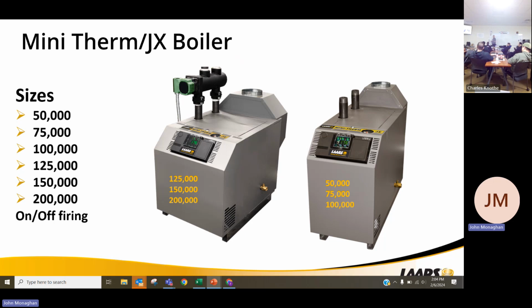Unlike the condensing products, it's on-off. There is no modulating. It's all the firing rate all the time, regardless of what is calling. One of the things I like to pitch about it, your 200,000 BTU boiler weighs 200 pounds. For you guys working in the city, it's a lot easier to carry that down the basement than its cast iron alternative. I say it often, lazy by nature, lazy man's boiler. It makes it very easy to carry it in.